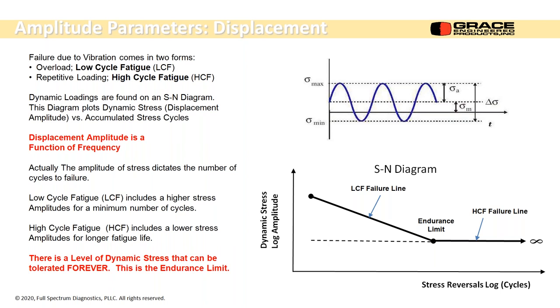You get a lot of low cycle fatigue from that big torque and that change in temperature really quick. So the overload capacity: these things really shoot to a high level when you turn them on. There's no soft start. They were never designed for that. And you start to get low cycle fatigue problems. Then you have to start limiting how many times you can do that a day or a shift before you're going to cause real big problems.